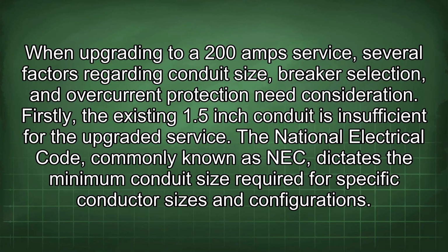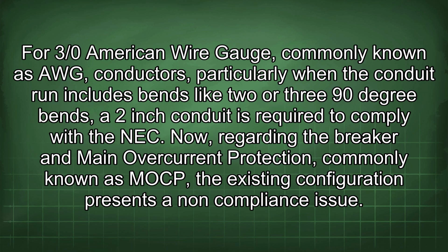When upgrading to a 200 amp service, several factors regarding conduit size, breaker selection, and overcurrent protection need consideration. Firstly, the existing 1.5-inch conduit is insufficient for the upgraded service. The National Electrical Code, commonly known as NEC, dictates the minimum conduit size required for specific conductor sizes and configurations. For 3/0 American wire gauge, commonly known as AWG conductors, particularly when the conduit run includes bends like 2 or 3 90-degree bends, a 2-inch conduit is required to comply with the NEC.